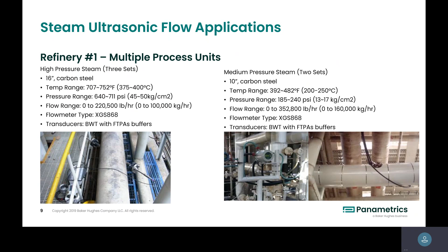Another example is medium pressure steam - a 10-inch line, about 200 pounds of pressure, with rangeability going to 0 to 350,000 pounds per hour. Again, transmitter style, BWT technology, FTPAs. You can see how they're installed in the picture here, with the nozzles installed as part of the piping. We sometimes provide the flow cell itself, or if something already exists, we can cold tap into the line to align with what's already in the field. This gives the flexibility of how you want to drive your system.